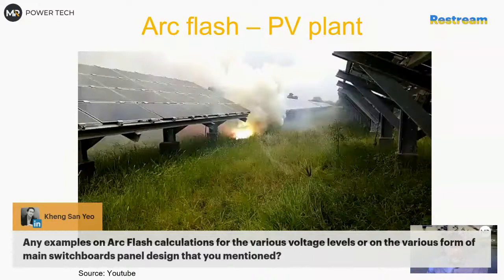There are some differences. That's why IEEE did a lot of testing. I'm not going to discuss IEEE because it's not going that technical. But the point is that sometimes you have insulation inside the panel where the arc can bounce back, so the arc is generally not easy to predict. That's why IEEE did over 2,000 tests, and they found that if you have some insulation below the cables or below the breaker, it might bounce back to you, which is called the VCBB configuration. If you have the main breaker, sometimes you see connections above which are not protected with anything, and they are directed towards you. So if you initiate an arc there, it will just come your way.